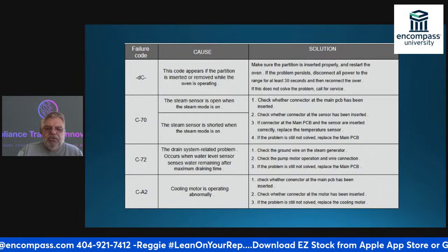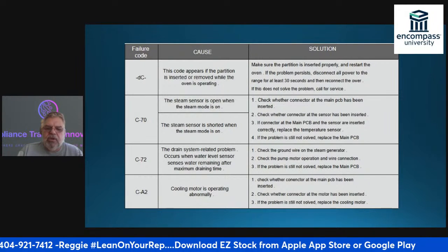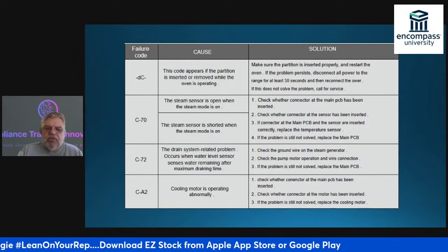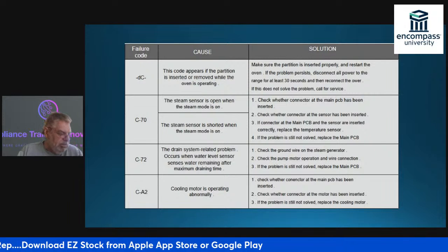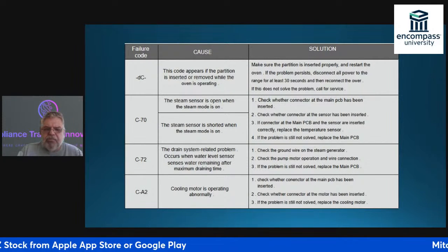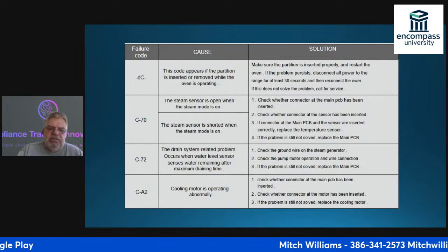So what am I going to do? I'm going to check the ground wire on the steam generator. Then I'm going to check the pump motor and the wiring harness to make sure that they are connected properly. If it's still not fixed, I'm going to have to replace the main PCB.